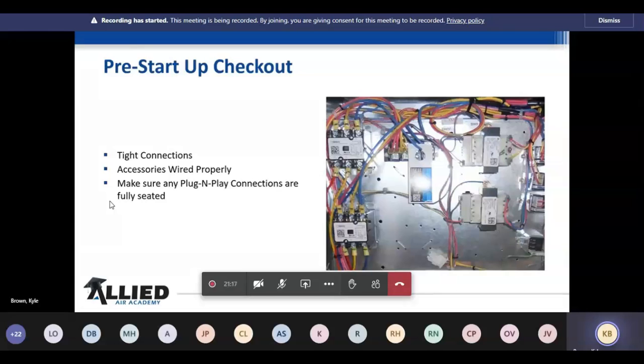Here's the most probably overlooked, because this control box looks good. Everything's nice and neat, nice and clean, put in there beautifully. All the little wire ties are up and everything's routed, and man, you gotta love it. But I'm going to check the lugs on that contactor, on both contactors, and I'm going to reach in there and make sure everything is good and tight. It doesn't take but a few minutes. And again, these pre-inspections are really important, because if those wires are just a little bit loose, it can cause some ghost voltage issues. It can cause, during long run times, all of a sudden, if you've got a VFD drive on this and one of these is the blower contactors, well, that VFD drive can kick out on a high amperage and there'd be absolutely nothing wrong with your voltage. The problem lies right here.